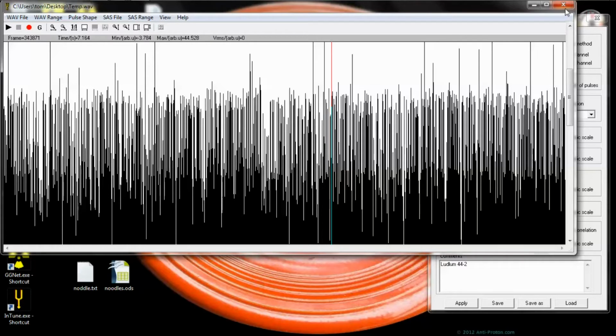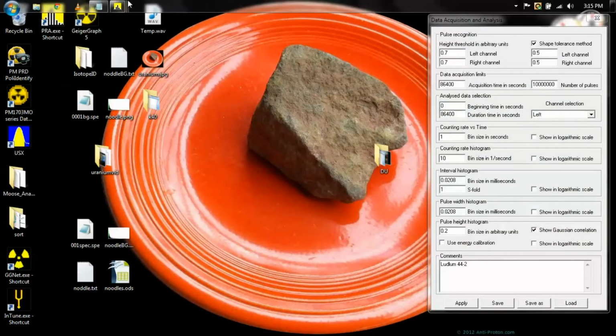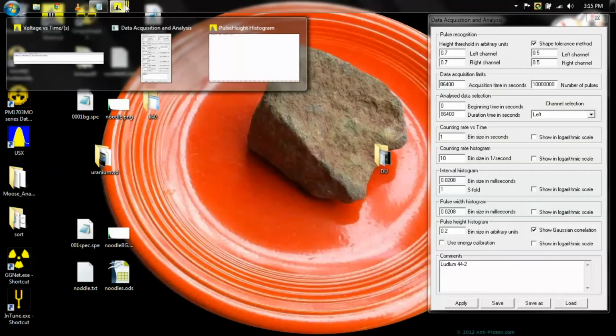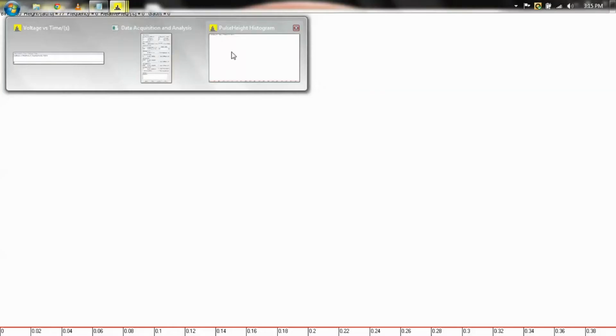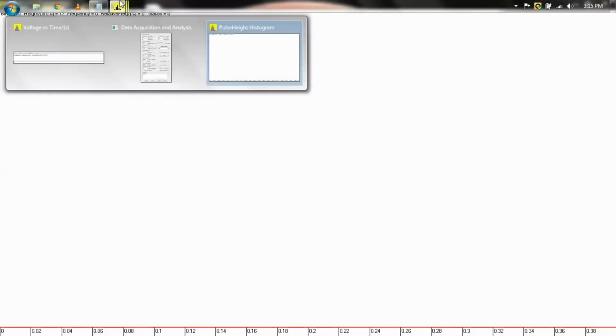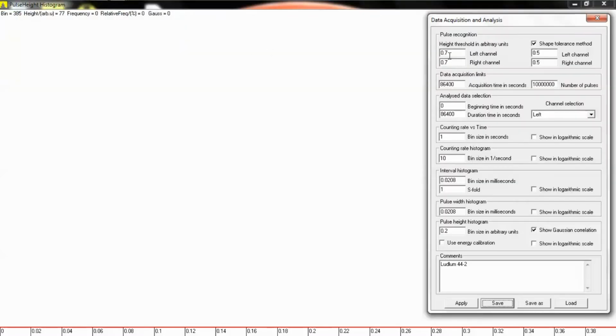So anyway, these sound pulses coming back are proportionate to the energy of the photon that hit them, because that's what the photomultiplier tube does. And so they'll be presented out here based on their energy. And this just tells me how high I want to reach. I don't want to go over 0.7 in arbitrary units. That would be 70 on that chart back there, I believe, if I have that right. I get this wrong sometimes, but that's okay.